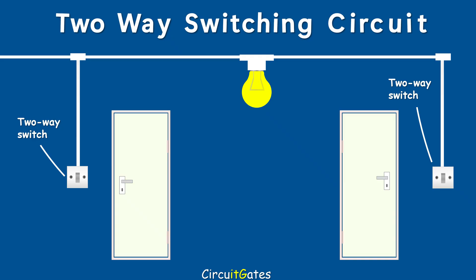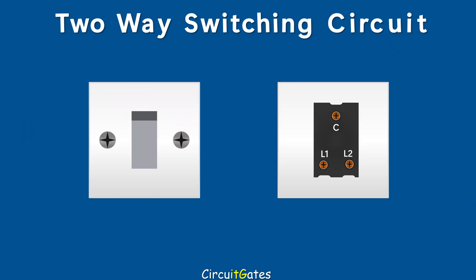The two-way switching circuit has two two-way switches. A two-way switch has three terminals: one terminal is labeled L1, another is labeled L2, and the last is labeled common. The common is the terminal where the live wire from the supply is connected, or the live wire going to the lamp from the switch is connected.